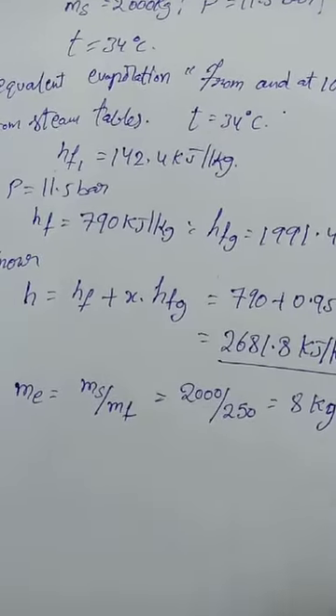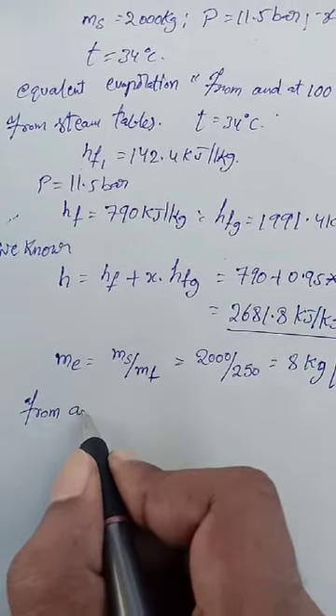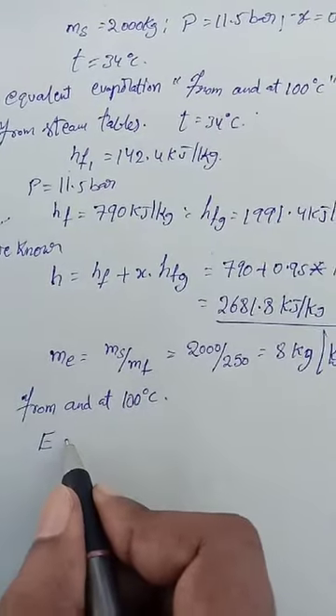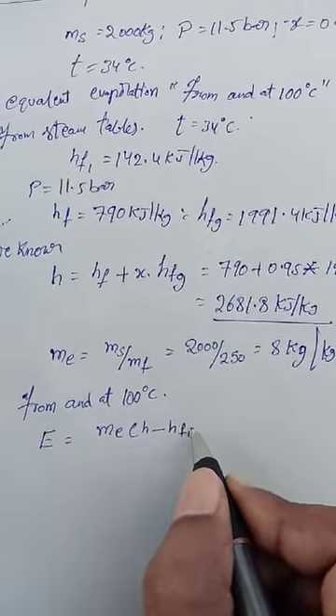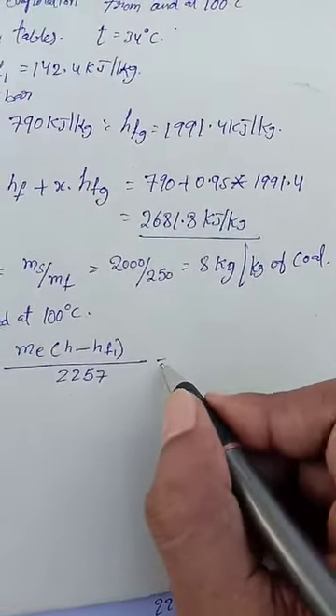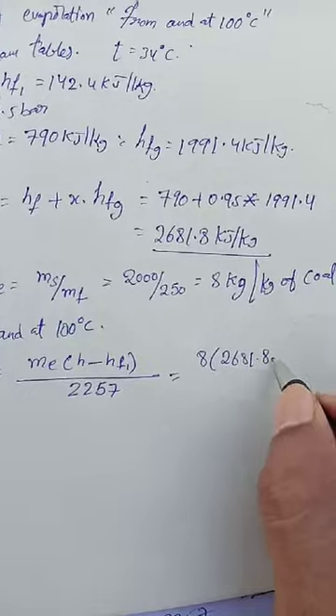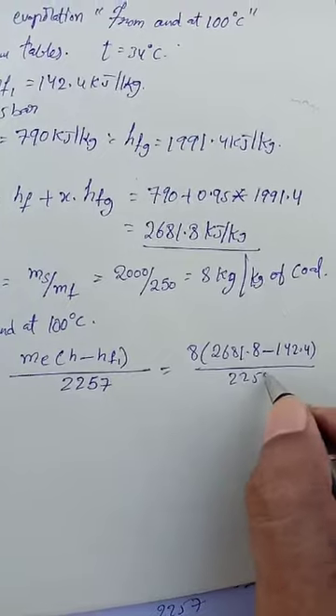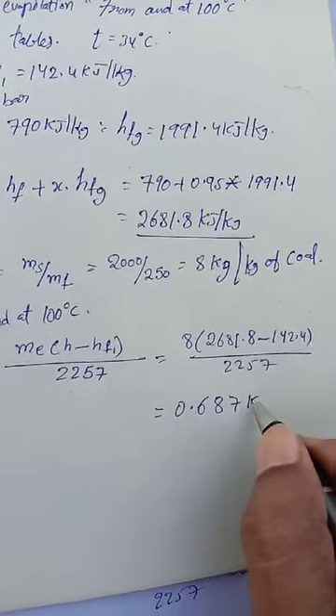Now we go for the equivalent evaporation from and at 100 degrees Celsius. The formula is: equivalent evaporation E = Me × (H − HF1) divided by 2257. Now substituting all values and calculating, we get the equivalent evaporation in kg per kg of coal.